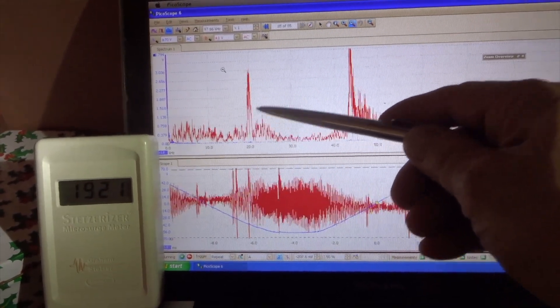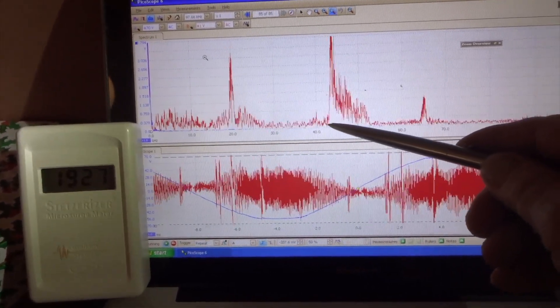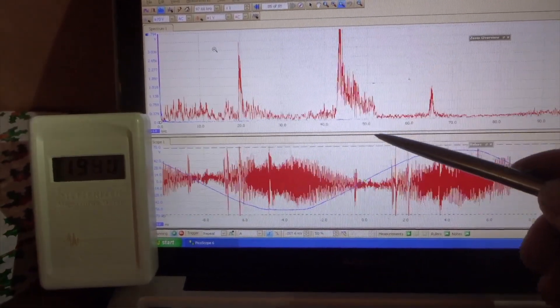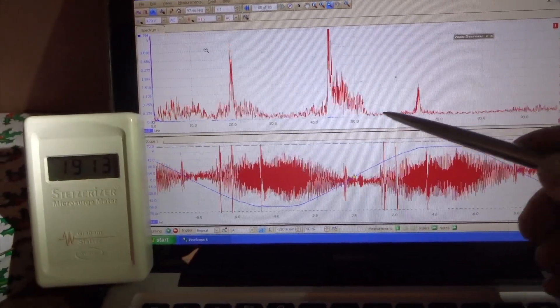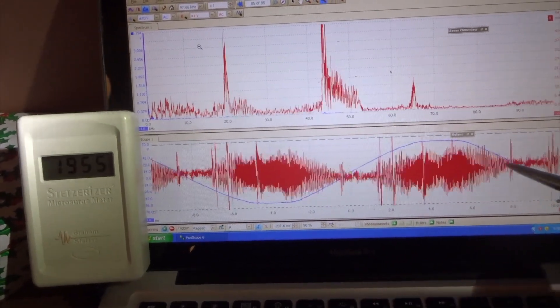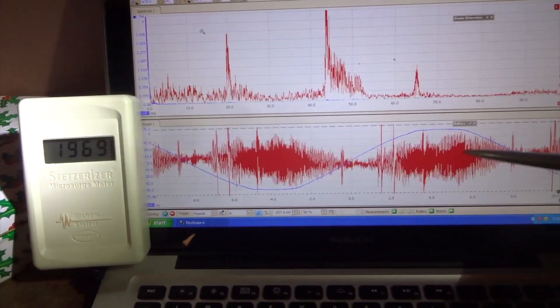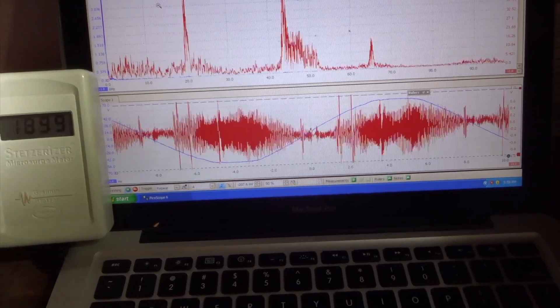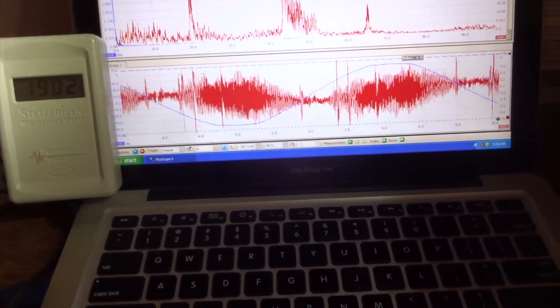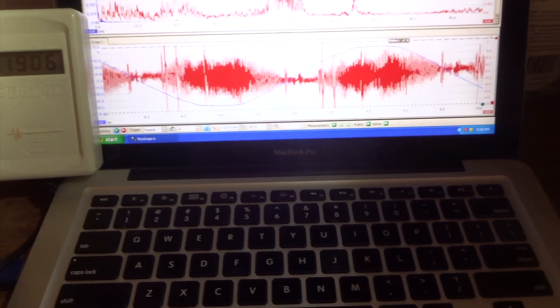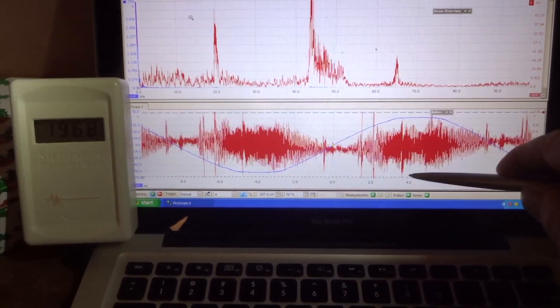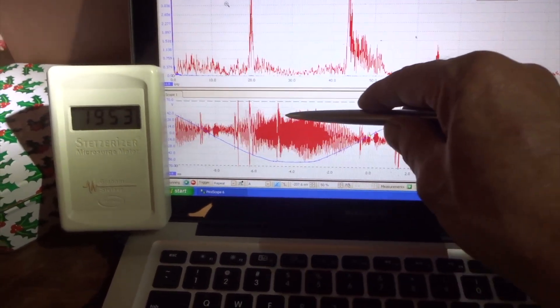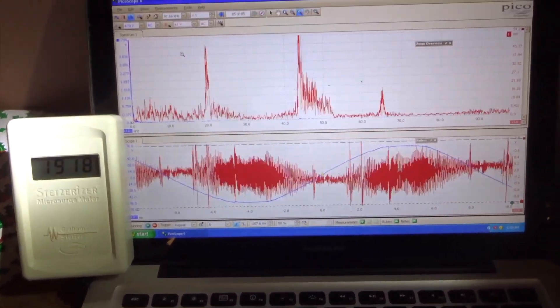We're getting a big spike at 20,000 cycles per second and also about 43,000 to 53,000 cycles per second and one out here about 65. This is the actual waveform. The blue is the 60 cycle, the red is the dirty electricity. The voltage amplitude we're getting is about 1.6 volts, 1.7 volts peak to peak, and the frequency is about 20,000 cycles per second.